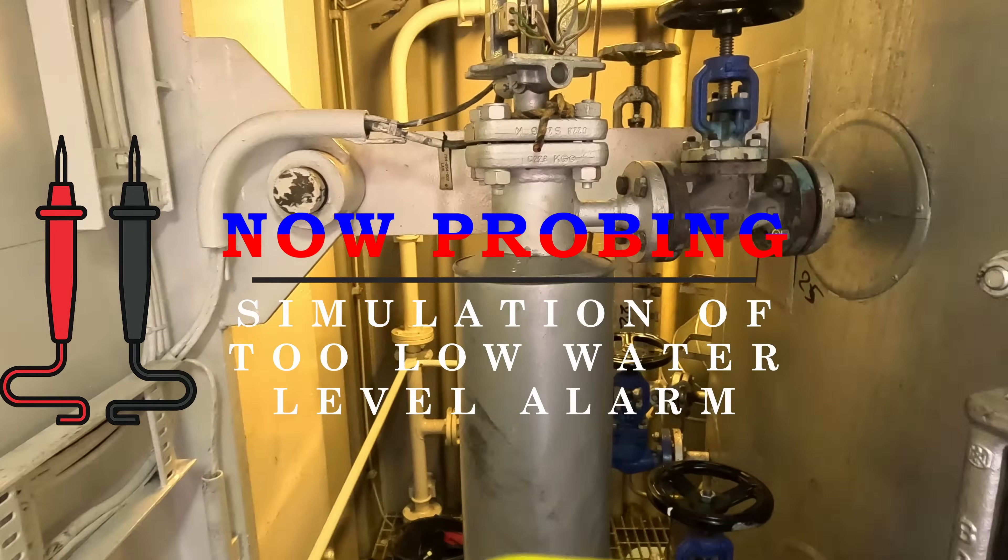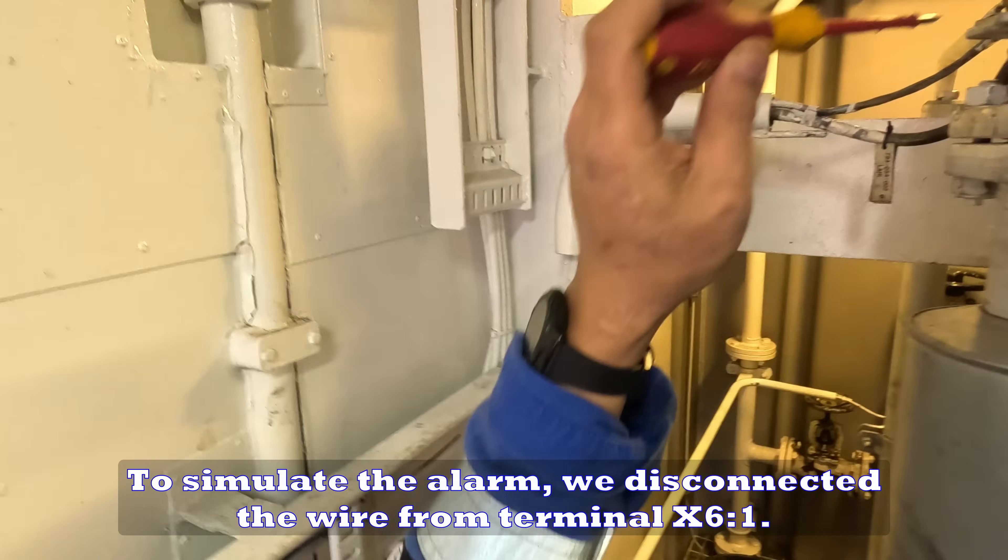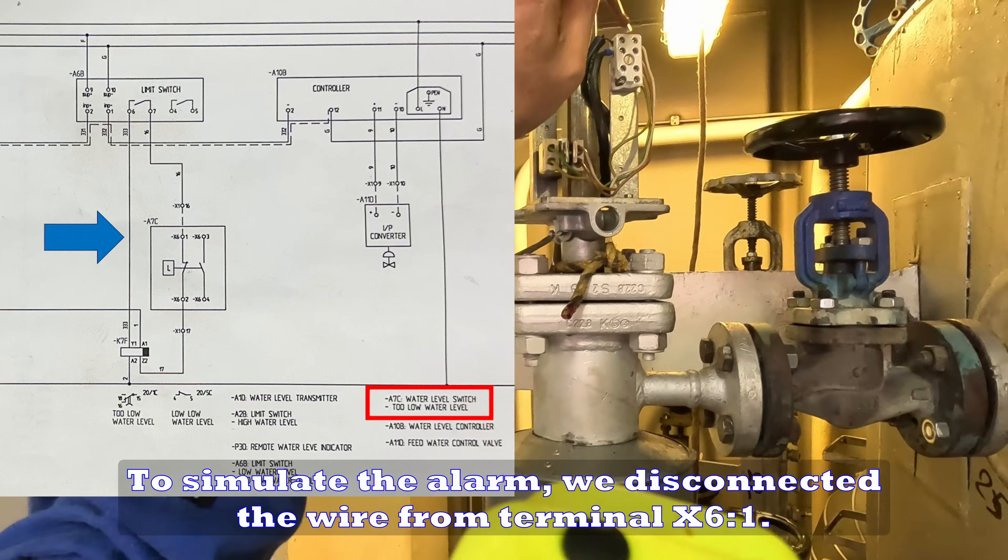Now probing simulation of too low water level alarm. To simulate the alarm, we disconnected the wire from terminal X6:1.